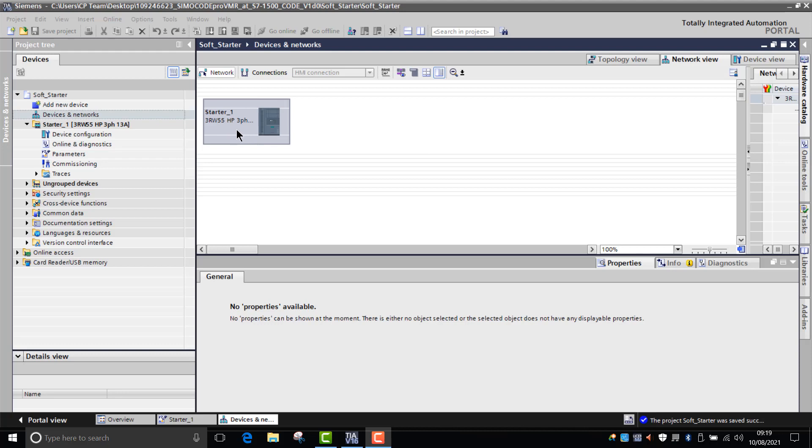It's a maintenance function which is integrated into the soft starter. You can drive off the outputs which are integrated into the soft starter, a reversing pair of contacts, and you can cycle the unit into forward and reverse, which would unblock a pump in, say, a sewage works factory. This function is specifically designed for water treatment works and it is a great feature to have because it dramatically reduces the amount of downtime if you're regularly using this maintenance function.